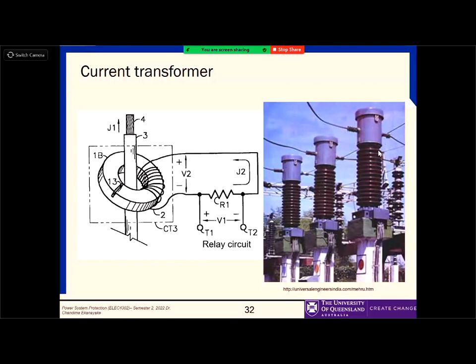And why do you need these big insulators mounting it? For insulation. Typically the voltage of this line is around 66 kV if it's a sub-transmission system, or 132 kV or 220 kV. It's very, very high voltage. So to have that clearance between the ground and the live component, you need this sort of insulation.